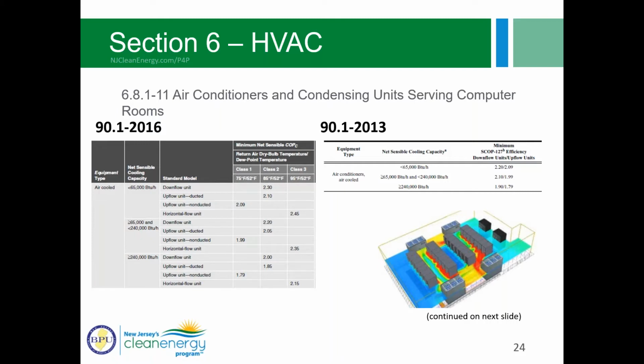Going on to this, the 2013 version had the cooling capacity for air-cooled units. And you can see it has downflow and upflow units, and we have these three sizes. So in 2016, it's the same air-cooled equipment types. They still have the same three size categories, but now they've differentiated between the upflow units to have ducted or non-ducted, and there's also a horizontal flow unit. Also, now we have these different class ratings of where these units are rated.